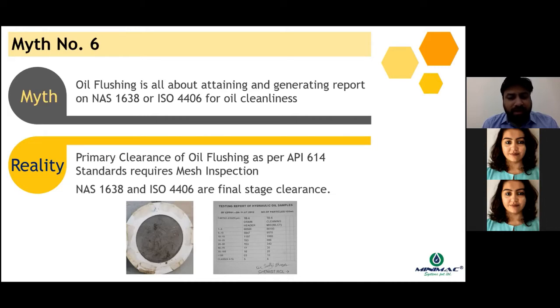The results on the NAS and ISO tester were pretty good, in the range of NAS 5, NAS 6. However, the mesh screen told a different story, because the mesh is actually handling the entire flow rate which you are feeding into your pipeline system. It is normally installed for inspection on the final return side of any of our flushing loops. Hence, it checks the contamination which is returning from the piping loop in totality, while the NAS and ISO 4406 tests are performed on a very small sample size, which might be between 100 milliliters to 500 milliliters.